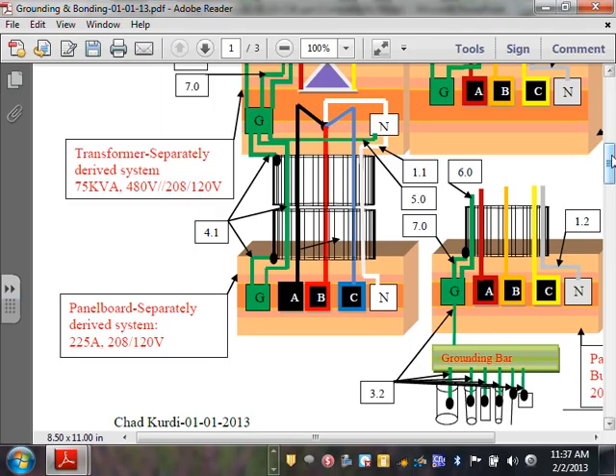Now this conductor here, this one, I call it 4.1 plus the main. And this is interesting. This one is really interesting. I call it 4.1. This is that bonding jumper on both sides, as well as this wire. Can you guys see it? Typically you need that conductor. This conductor, guys, is called a supply side bonding jumper. Same thing like at the service. They call it supply side bonding jumper. Very easy. Can you guys see that? This conductor here, from the transformer into the panel, in 2011, they call it supply side bonding jumper.